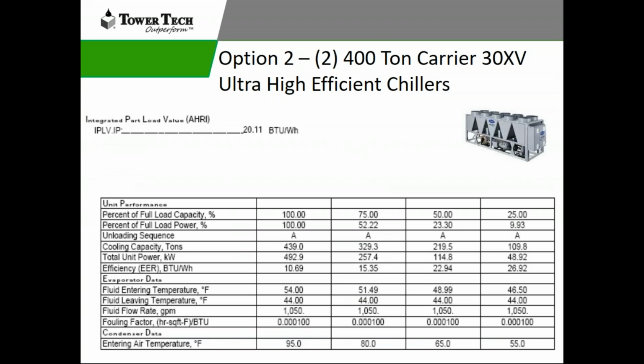So our option two system is going to be two 400-ton ultra high efficiency Carrier 30XV chillers. Now this has a part load value of 20.11 BTU, so when we put it into kW per ton, it's operating at about 0.59 kW per ton, and it's an air-cooled system. Our air-cooled systems have gotten so efficient that, with the cost of water, you sometimes find this is a more economical install and a better solution for an owner.